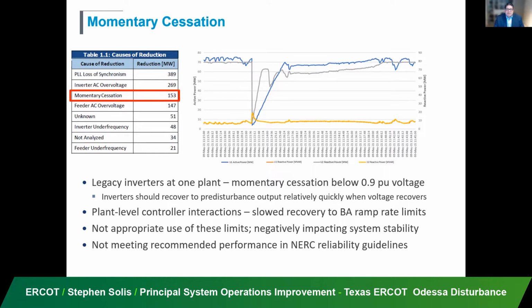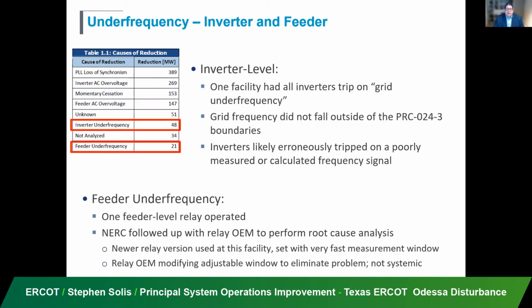So if there is momentary cessation, we still would like those megawatts to return to the system as quickly as possible, hopefully within 1 second. And for them to do that, there are other settings that have time delays. And sometimes those time delays or ramp rates back are just default settings that can be adjusted so that there's an improved performance after the momentary cessation occurs. So it goes into momentary cessation, the fault clears, and it's able to respond and recover back. That's what we want. And those are the changes that we have to work with the manufacturers and the plants to make.